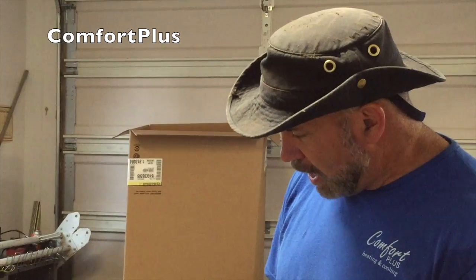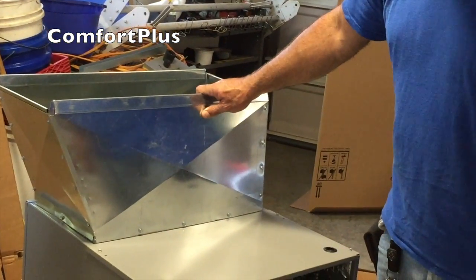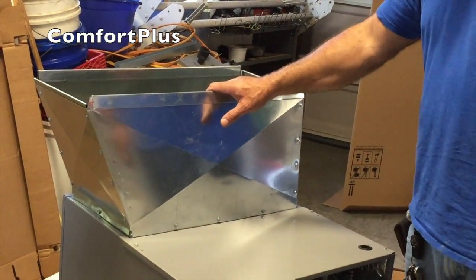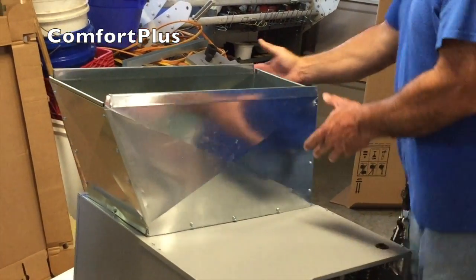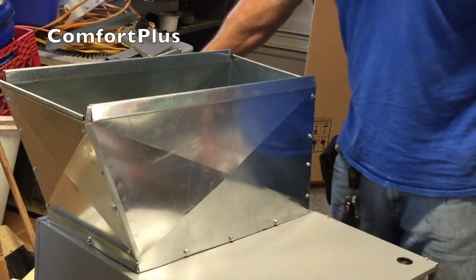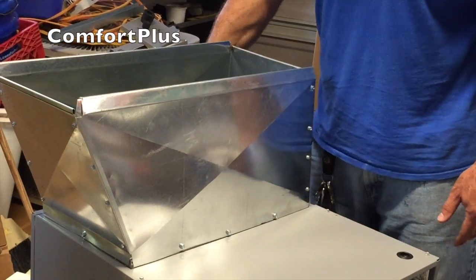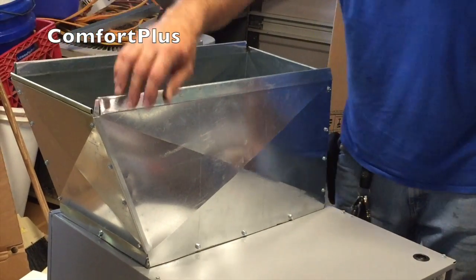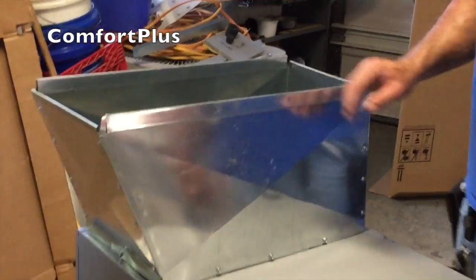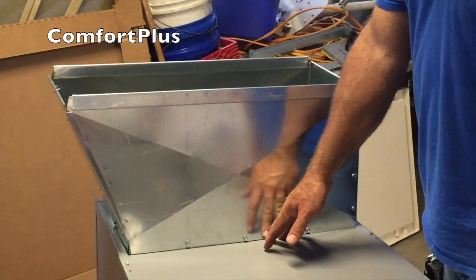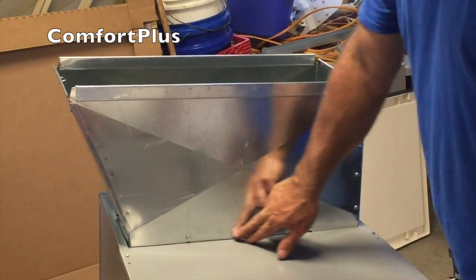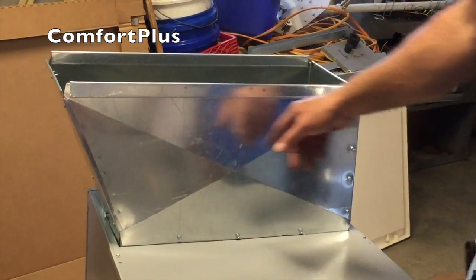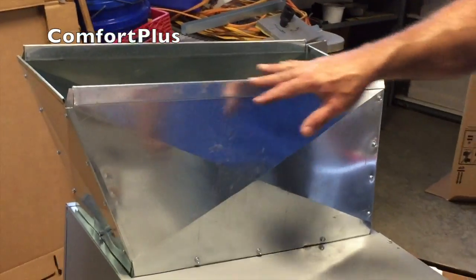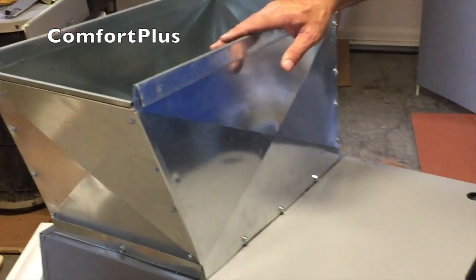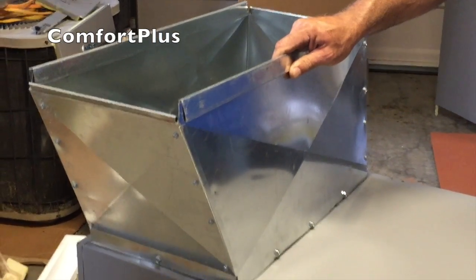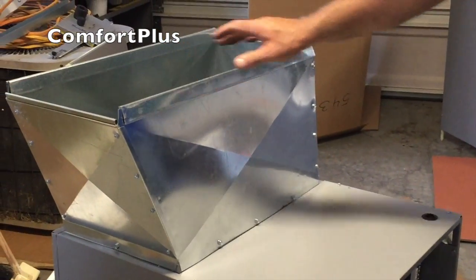Okay, this is the top part of the air handler. Again, I take it apart to make it easy to work on. This is my transition. I made it out of 3 pieces of metal. This is the only right angle on it, so I used it, bent a piece of metal and made that to start with. Then I could measure the actual lengths of these angles in order to get the right size piece of metal. So I've got it screwed to the flange on the air handler already. What I'll actually do is use mastic tape right here, and then I'll put mastic on all the other seams on it. And I will insulate this portion, leaving this joint right here to be made underneath the house and attached to the trunk duct over there.